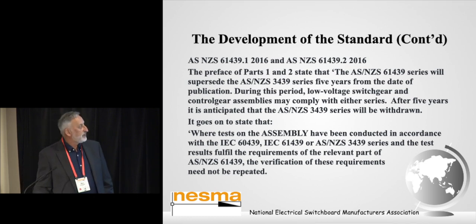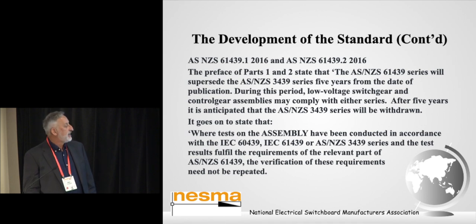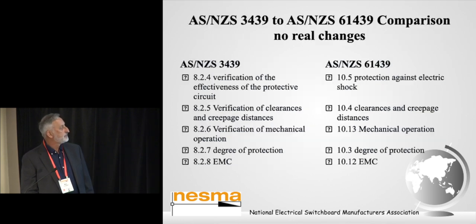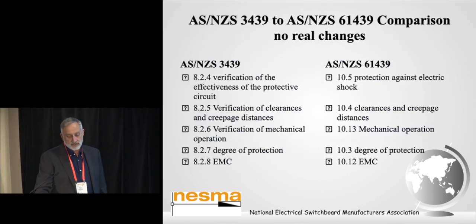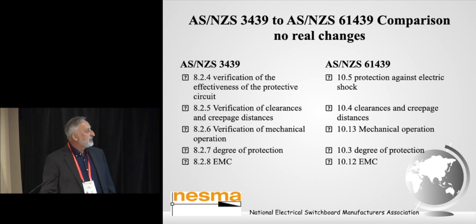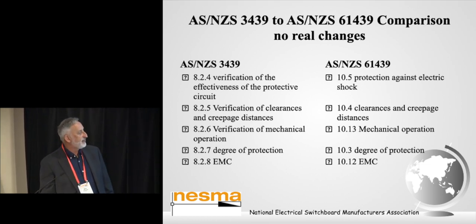That particular document, the 2016 AS, says where tests on the assembly have been conducted in accordance with IEC 60439, 61439, or the AS-NZS 3439 series, and the test results fulfil the requirements of the relevant part of AS 61439, the verification of these requirements need not be repeated. So what I thought I'd do is just a little quick comparison. In these particular clauses, we'll look at the current standard.